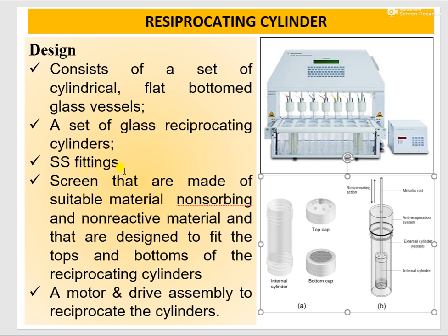There will be stainless steel fittings, screen that are made up of suitable material, non-sorbing and non-reactive material, and that are designed to fit the tops and bottom of the reciprocating cylinder.